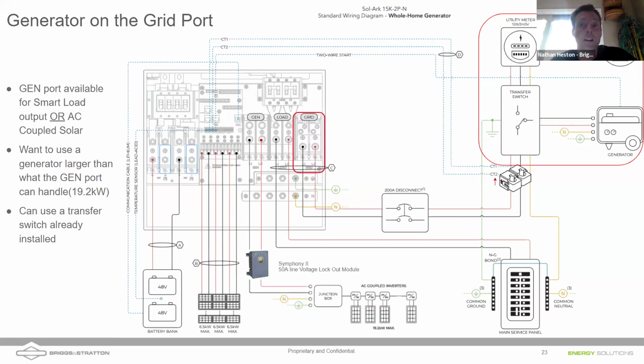Now, not everybody does it because it's about $600 for a bypass transfer switch. But if you put a manual bypass transfer switch in, you can eliminate that problem, Jim. So just look for that. You can look for a 3-position switch. It could be off, it could be set to the inverter, or it could be set to bypass the inverter and go straight to load. So that's allowing the grid to pass around the Sol-Ark inverter in the situation in which maintenance needs to be done.